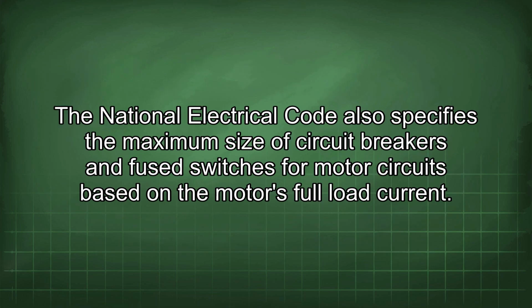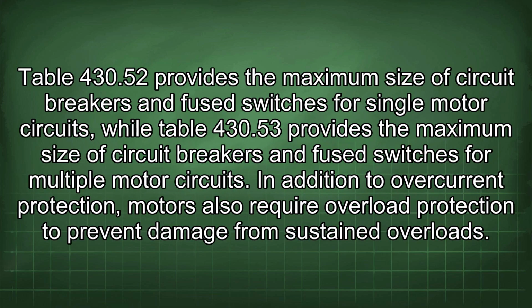The National Electrical Code also specifies the maximum size of circuit breakers and fused switches for motor circuits based on the motor's full load current. Table 430.52 provides the maximum size of circuit breakers and fused switches for single motor circuits, while Table 430.53 provides the maximum size of circuit breakers and fused switches for multiple motor circuits.